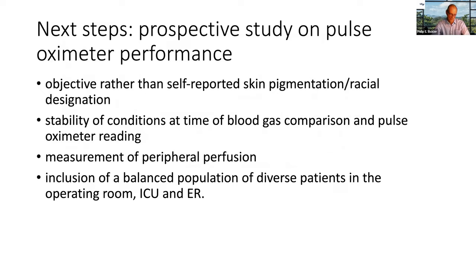So what our next steps are is we are planning a prospective study on pulse oximeter performance. And it's designed to overcome the problems that were present in those four retrospective studies that have been so influential. And we're going to use an objective rather than self-reported skin pigmentation scale, rather than racial designation. We're going to make sure that pulse oximeters are reading under stable conditions and that we know the perfusion index.